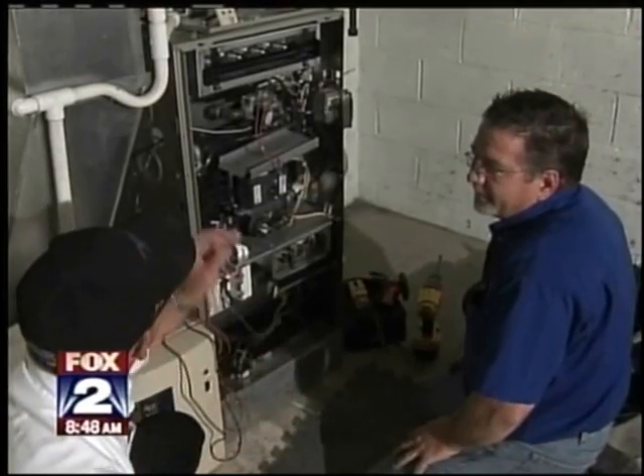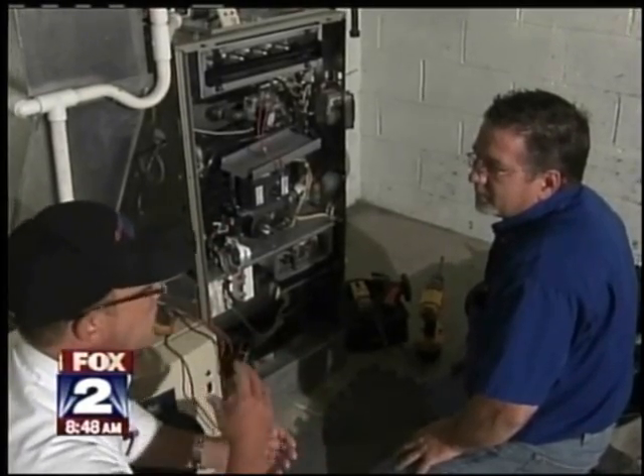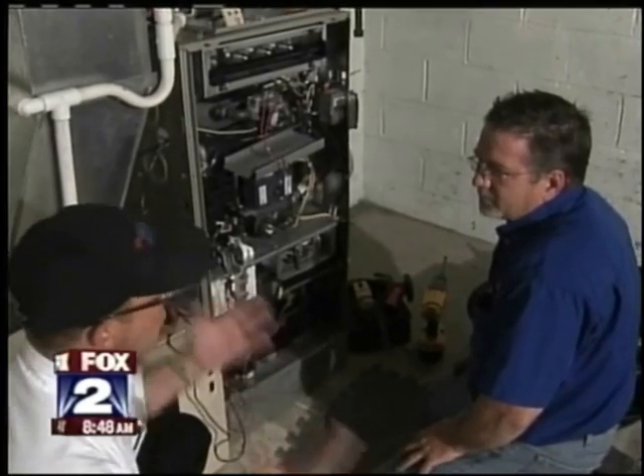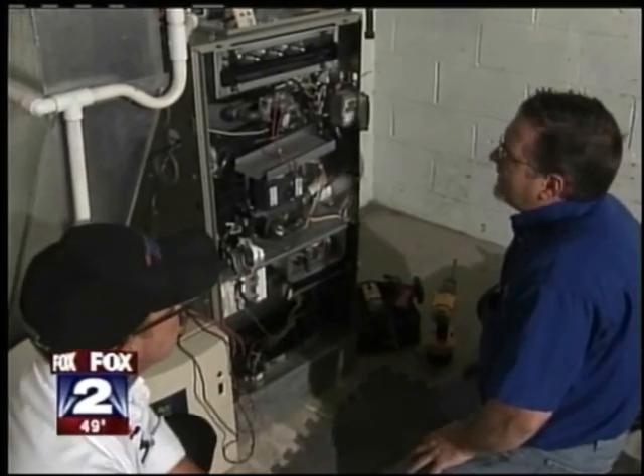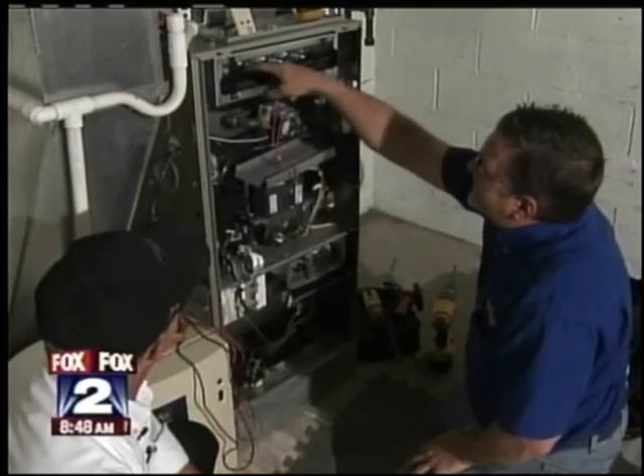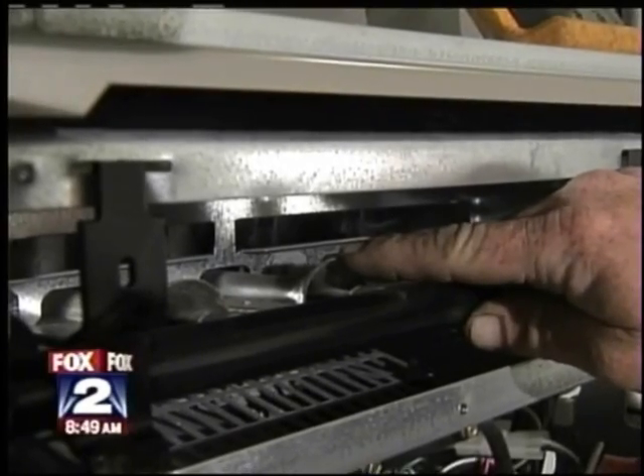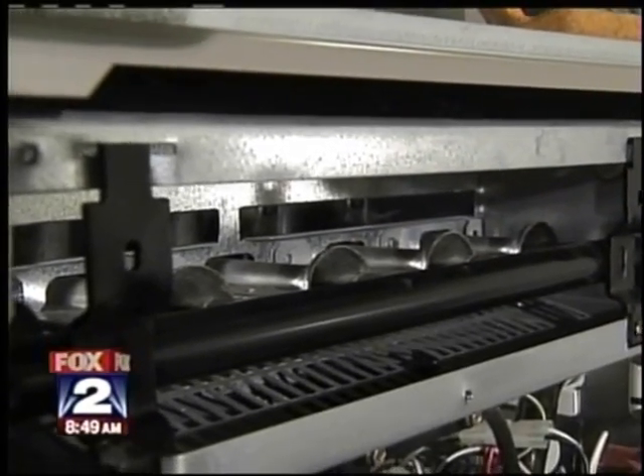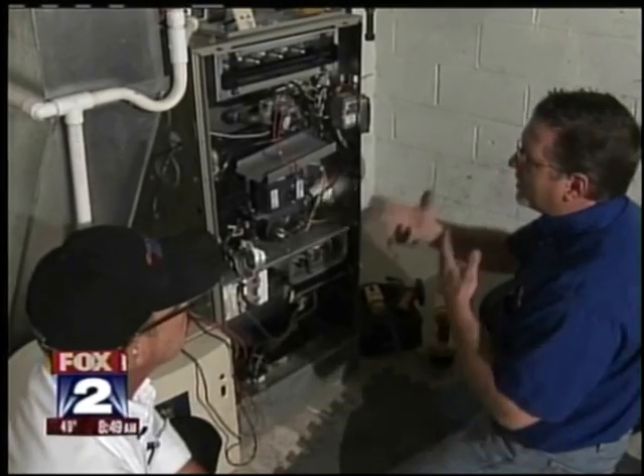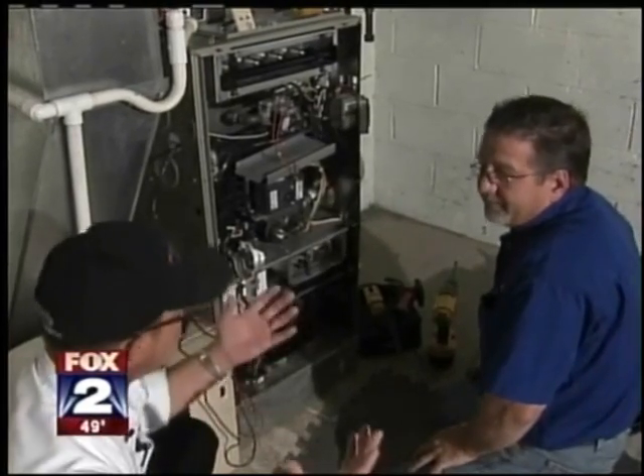I've heard people talk about their furnace booming when it comes on — is that burner related? Yeah, generally that happens when you've got plugged orifices right at the tips of the burners, or the ends getting dirty, which causes a delayed ignition. And there you get the boom.